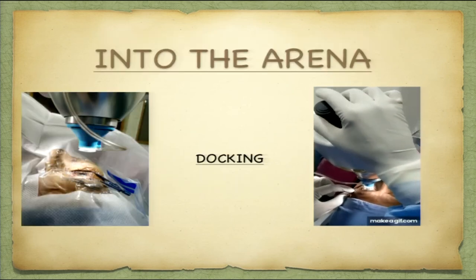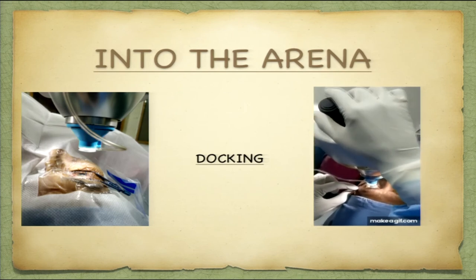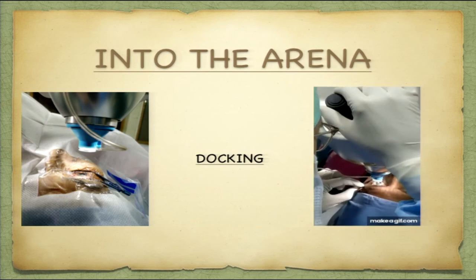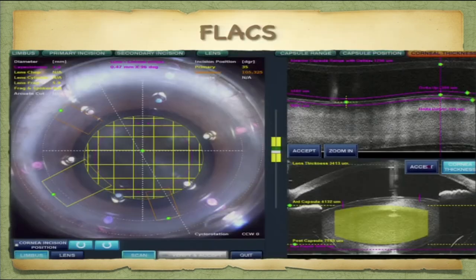Docking is important because you have to center it on the eye — once that is done, the next steps become easier: the capsulotomy and the lens fragmentation. This is how the live OCT works — it is a real-time 3D OCT giving you a picture from the anterior surface of the cornea to the posterior surface of the lens, all in one image from top to bottom.